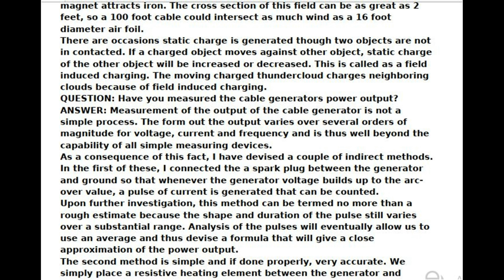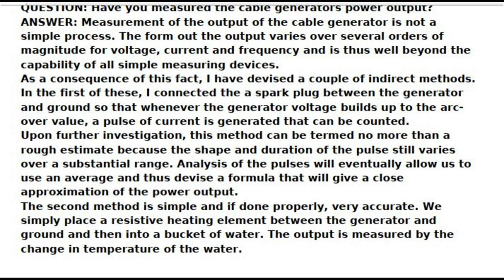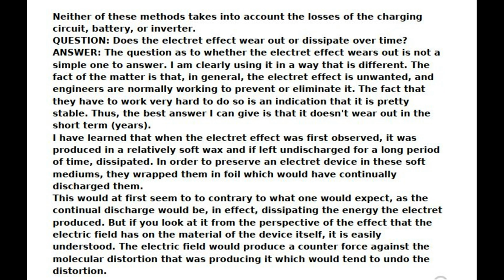The second method is simple and, if done properly, very accurate. We place a resistive heating element between the generator and ground, and then into a bucket of water. The output is measured by the change in temperature of the water. Neither of these methods takes into account the losses of the charging circuit, battery, or inverter.